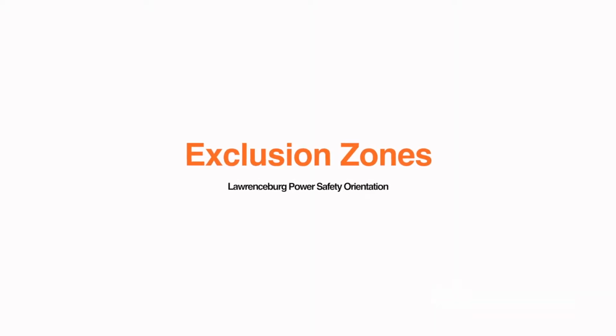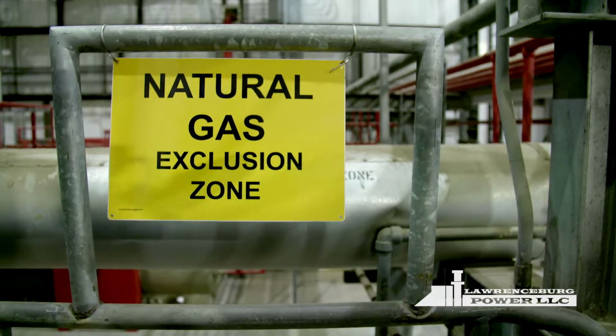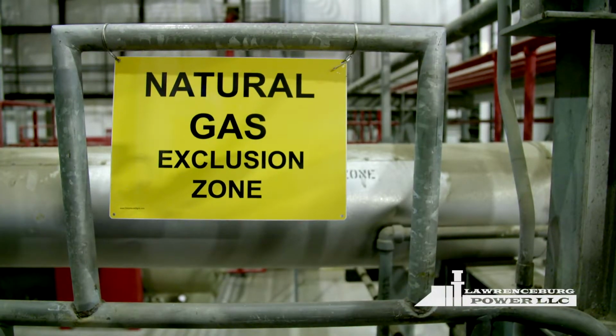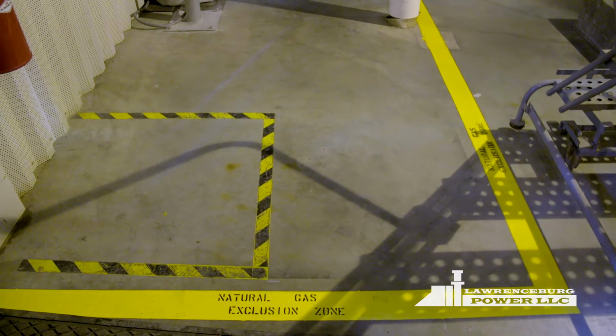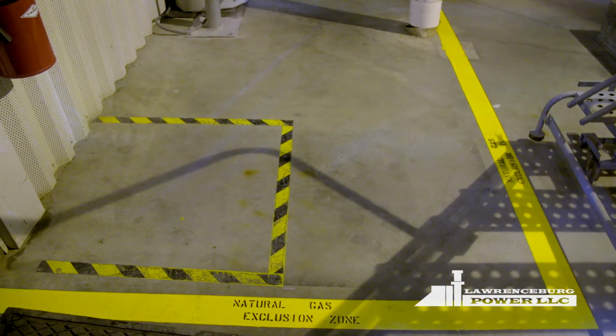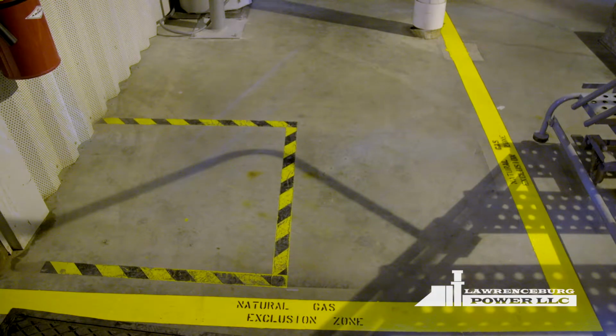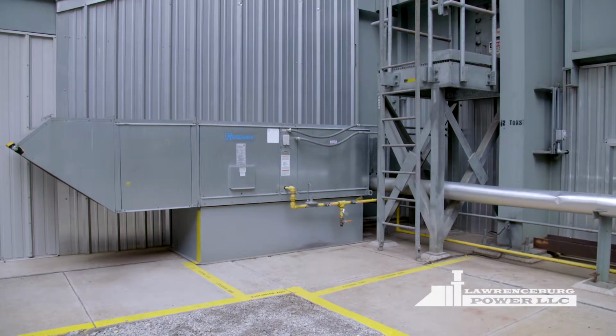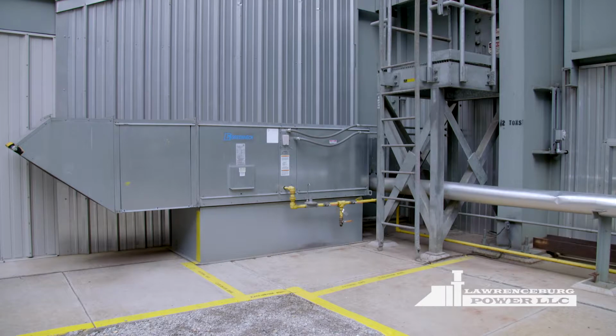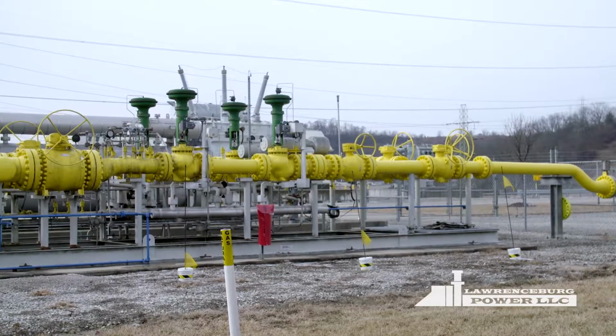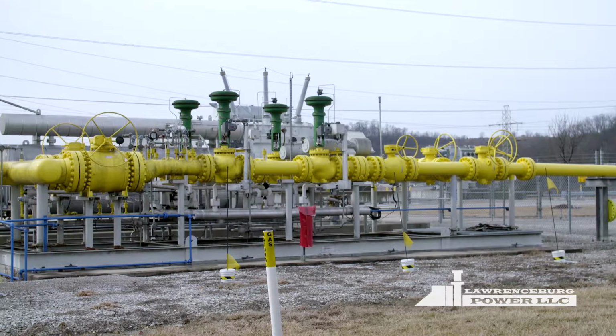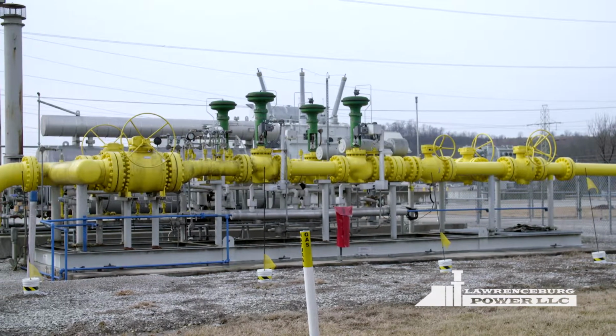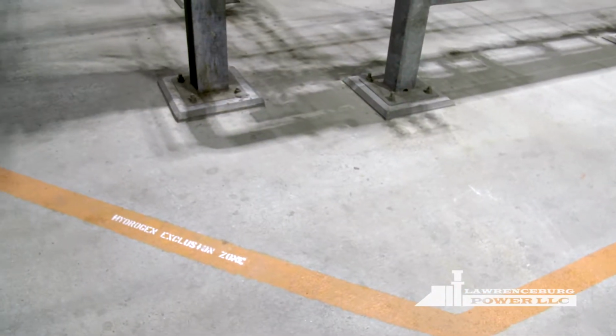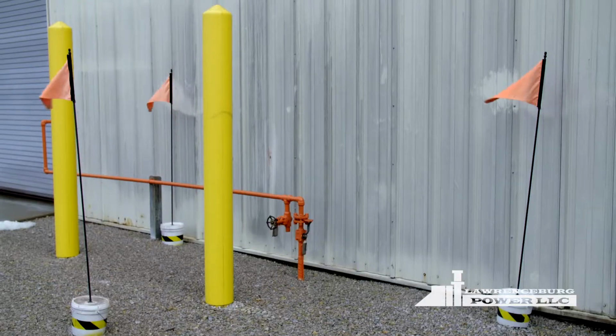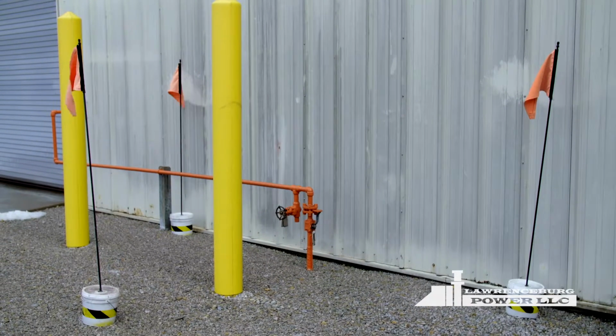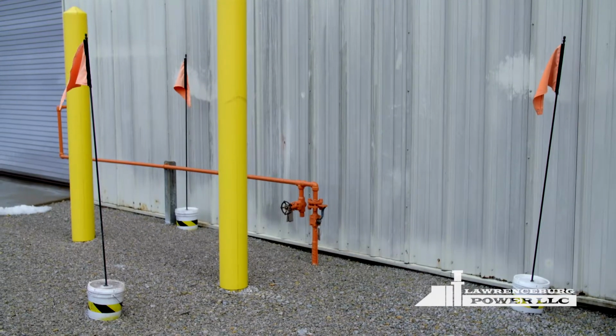Exclusion zones. Hazardous area exclusion zones are invisible three-dimensional spheres around gas lines, vents, flanges, valves, and other potential leakage sources. Division 1 denotes areas where flammable concentrations of gas can exist under normal operating conditions, such as vents and drains. Division 2 denotes areas where flammable concentrations can exist under abnormal operating conditions, such as a leaking pipe flange or fitting. Extension cords, power tools, portable heaters, and other ignition sources are prohibited in these areas.